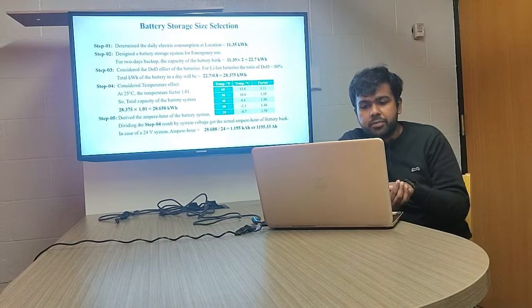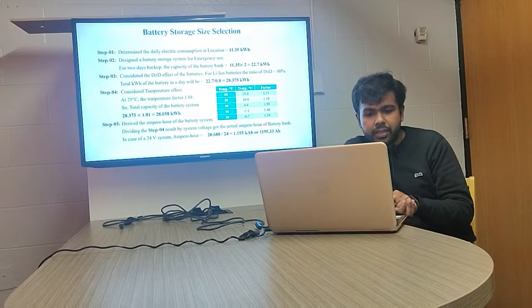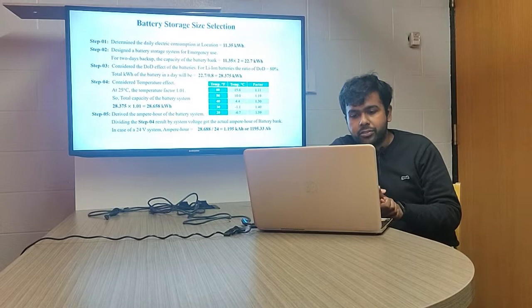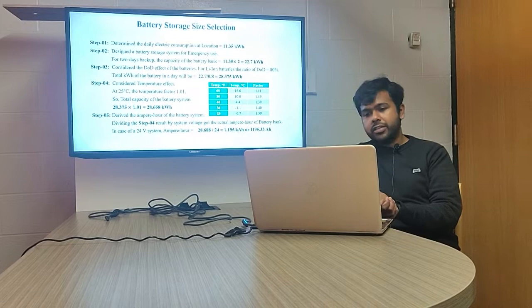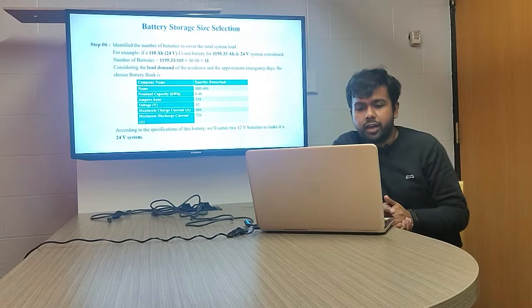At 25 degrees Celsius room temperature, the temperature factor is 1.01, and we used this value in our calculations. In step five, we calculated the ampere-hour of the battery system by taking the value from step four and dividing by the total battery system voltage of 24 volts, obtaining 1195.33 ampere-hours, which is the total ampere-hour required to back up the whole system.